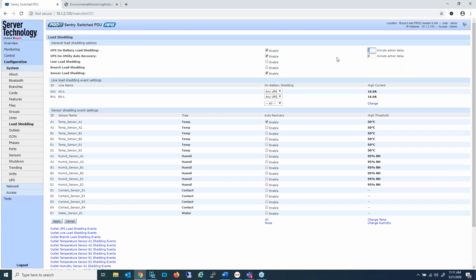We do have an option to have a delay. That is, when an event occurs, when a UPS loses utility power, you can specify a delay before pre-selected outlets, which we'll look at next, actually switch off. You then have an option as well for on utility auto recovery. And if enabled, what that means is when utility power is restored, we will recognize within 10 seconds that the UPS is back on utility power, and we will automatically switch the outlets that had switched off. We will switch them back on. And again, you do have an option to specify a delay.